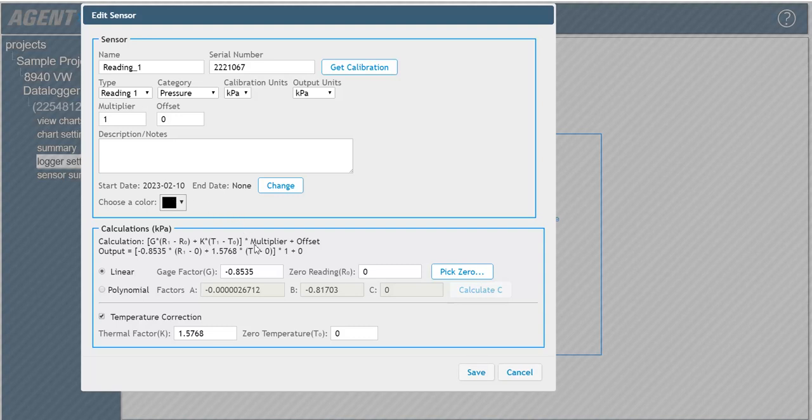If the gauge factor was not already downloaded from Geokon's online database, enter the linear gauge factor from the calibration report provided with the sensor. Make sure the calibration units selected in agent match the engineering units of the gauge factor taken from the calibration report.